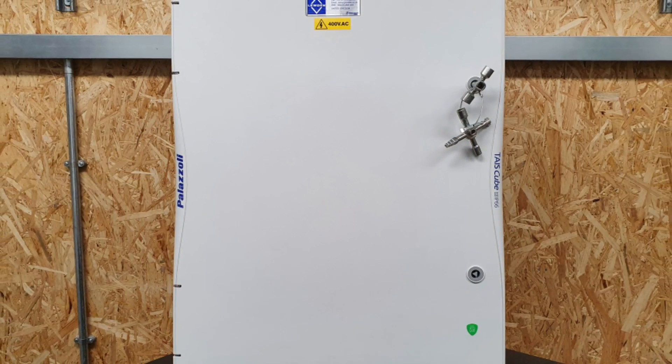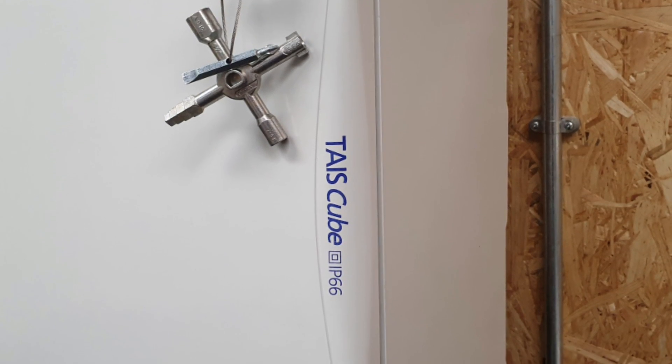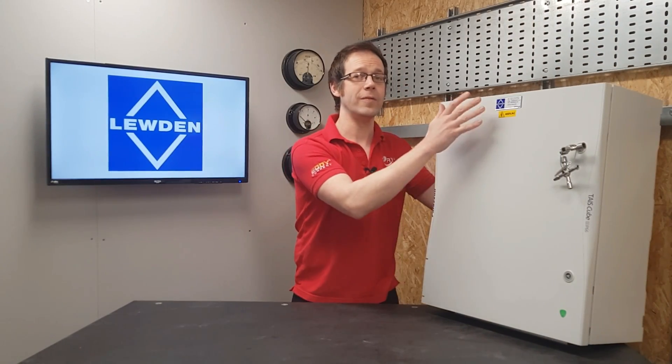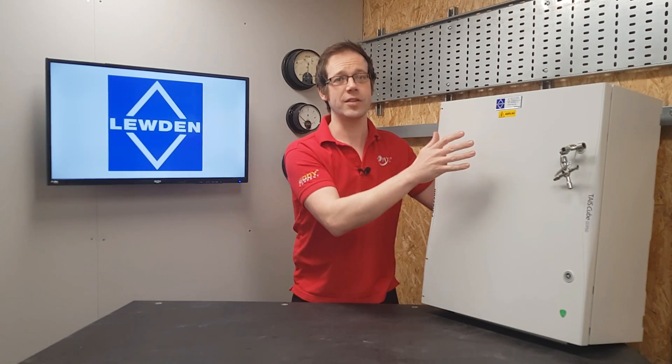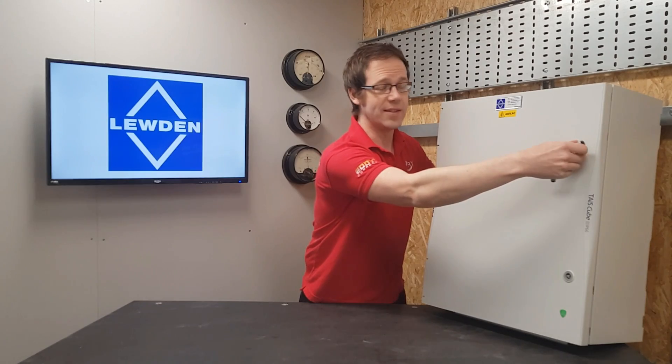I promised at the outset that we'd see something a little bit special, and it's right here. You may find yourself carrying out installs in environments where a higher than usual level of IP rating is required, and this is just an incredible solution. This is a three-phase and neutral board that has been made using elements of the TAIS Cube range featured in previous videos. When the door is closed and latched, it's got an IP rating of 66, meaning it's dust-tight and impervious to high-pressure water jets. This is a distribution board that means business.